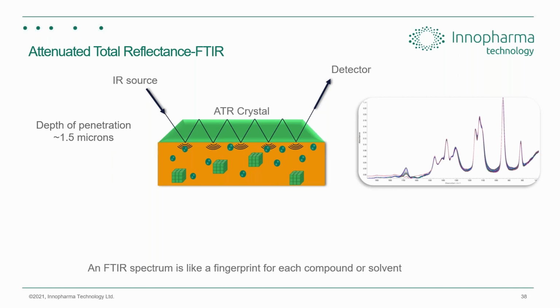But here, attenuated total reflectance is the other part. That's the part that allows FTIR, which is traditionally just a benchtop method, to deliver the light into the reaction vessel and collect signal from the reaction fluid itself. In this case, the infrared source is delivered, and the light bounces back and forth. There's total reflectance inside a crystal inside the reaction vessel, and the light is then collected by fiber optics and brought back to the detector. Light that's reflected from the sample solvent molecules tells us what those molecules are. So we use attenuated total reflectance FTIR to determine what things are still dissolved in the solution. Again, it produces a spectrum like we've seen.